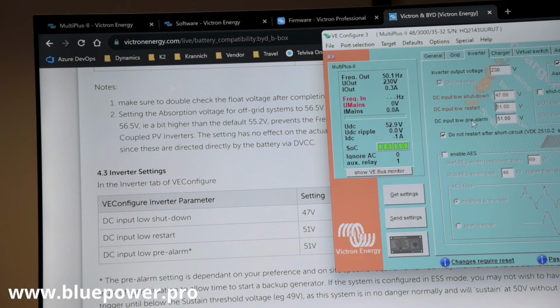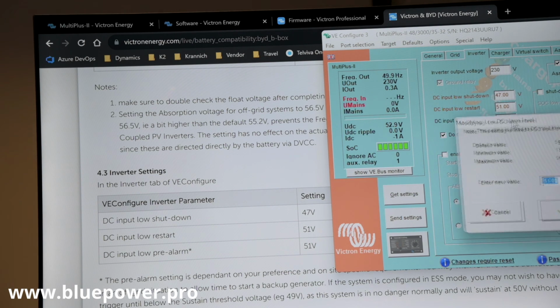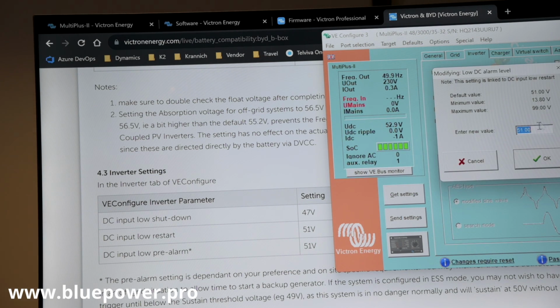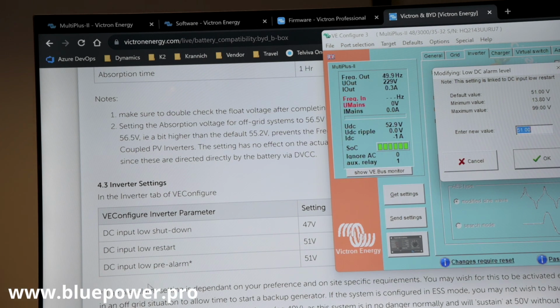Over here, next option is our DC input low pre-alarm. On the inverter, we've got a low battery alarm LED. This is the value at which that LED is going to start flashing. Over here in the manual, we can see that they've got a note on that, set to 51. Here they say the pre-alarm setting is dependent on your preference and on site-specific requirements. You may wish for this to be activated earlier or later.